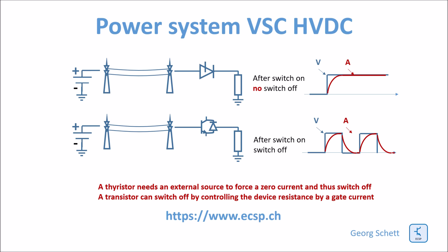The key difference is that you can switch on a thyristor, but switching it off cannot be performed by the thyristor itself. The thyristor needs a current zero to switch off, and this current zero has to be provided by the load. With VSC technology, the active switch can be switched on and off by changing its resistance from close to zero to close to infinite. Once a thyristor is switched on, the DC current flows and cannot be interrupted anymore — commutation can only be achieved by an external active oscillating load which forces the current through zero.